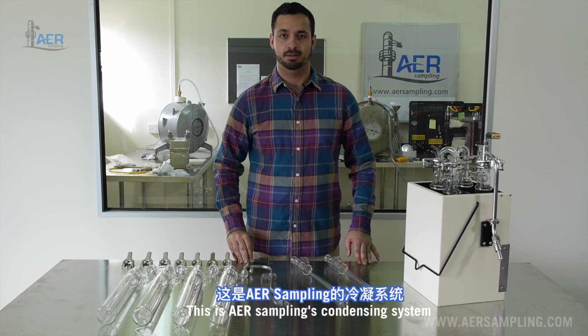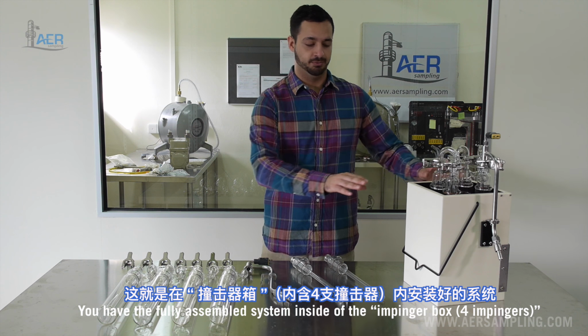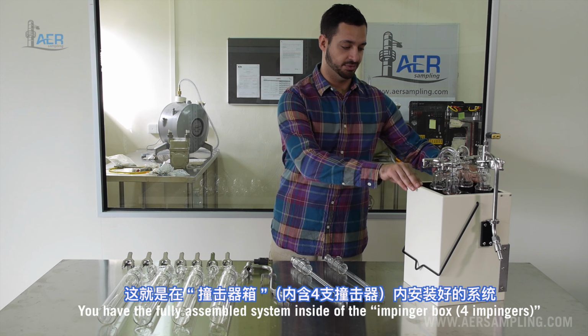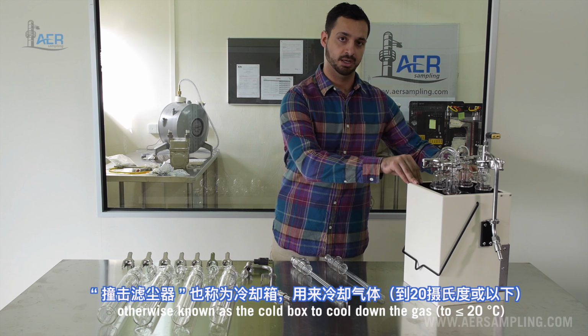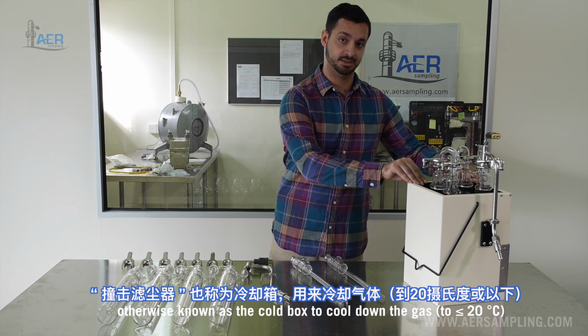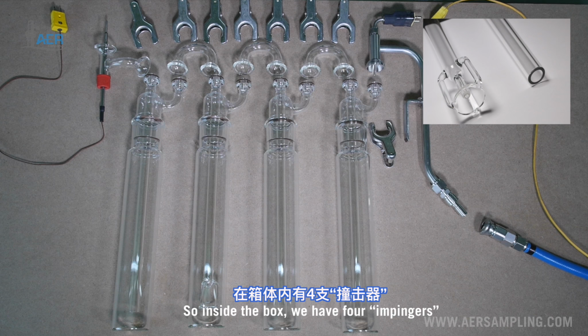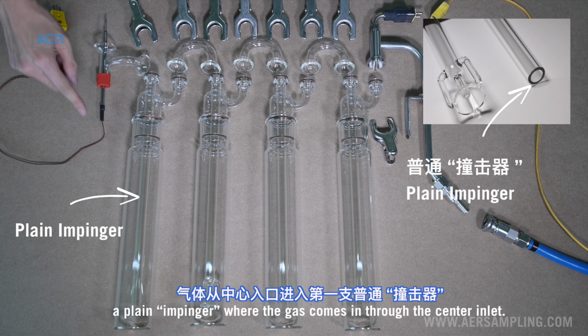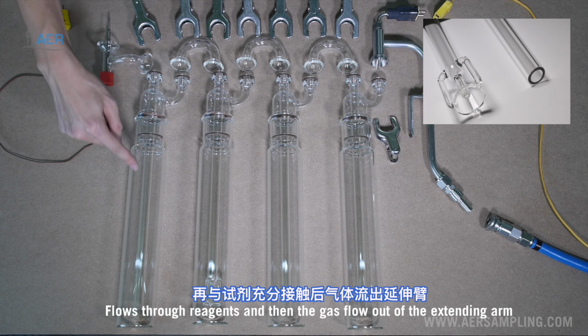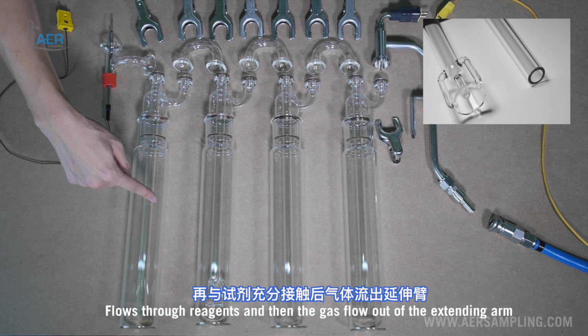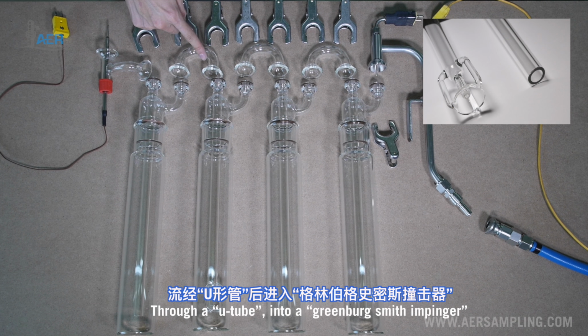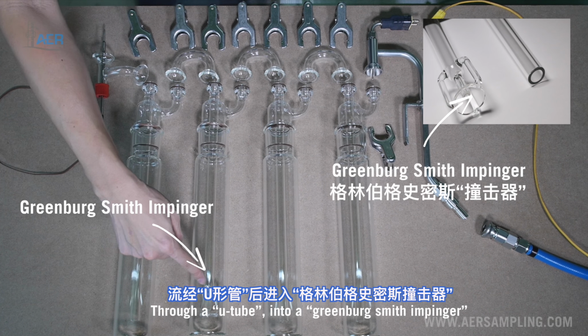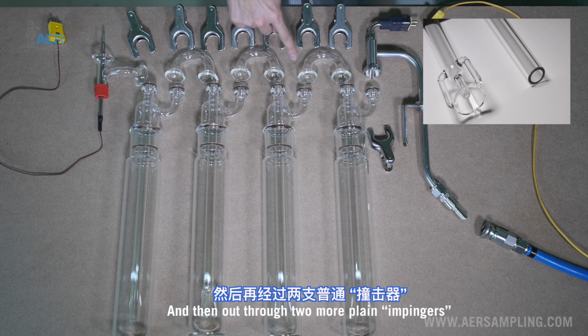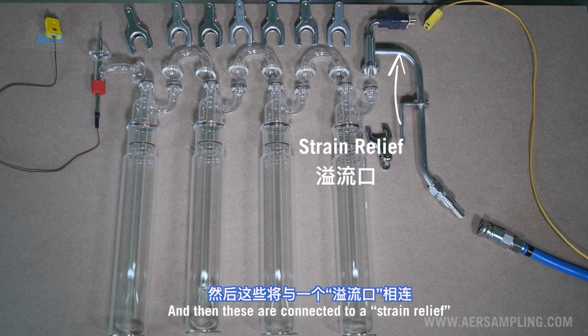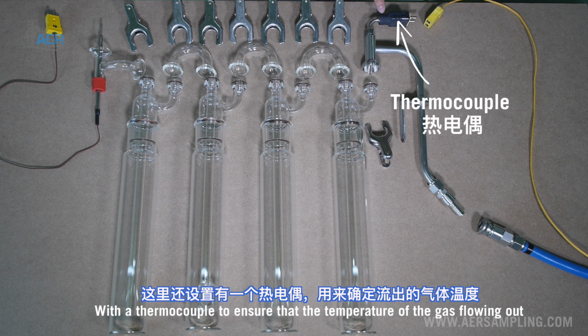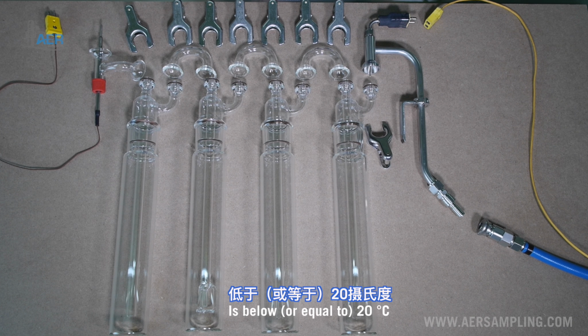This is Aer Sampling's condensing system. We have the fully assembled system inside of the impinger box to cool, otherwise known as a cold box, to cool down the gas. So inside the box, we have 4 impingers, a plain impinger where the gas comes in through the center inlet, flows through reagents, and then the gas flows out of the extending arm through a U-tube into a Greenberg-Smith impinger, and then out through 2 more plain impingers. And these are connected to a strain relief with a thermocouple to ensure that the temperature of the gas flowing out is below 20 degrees Celsius.